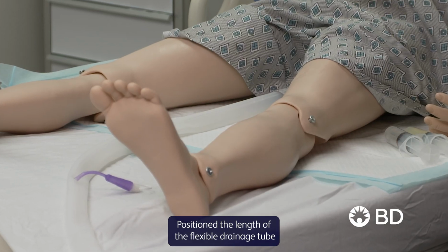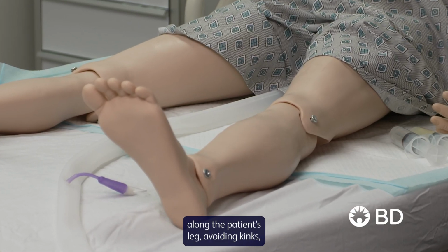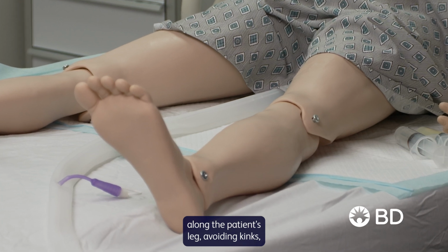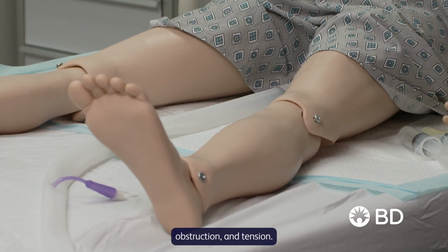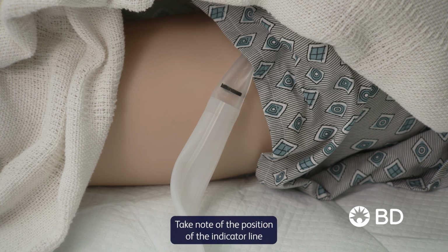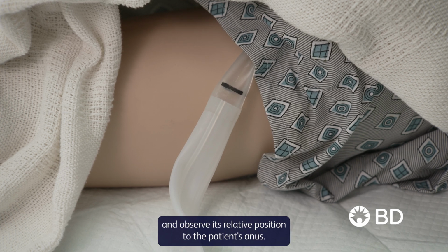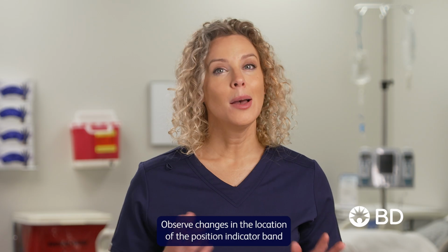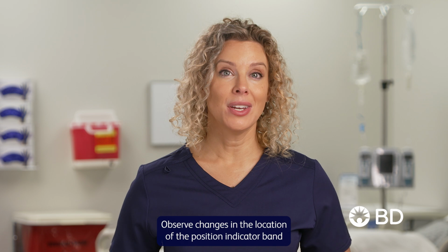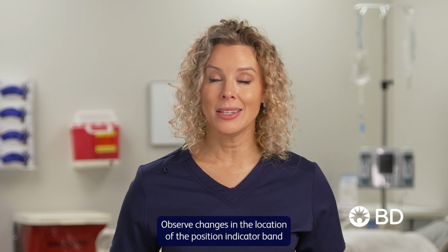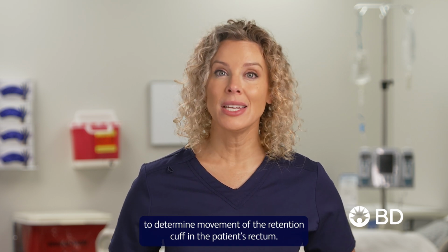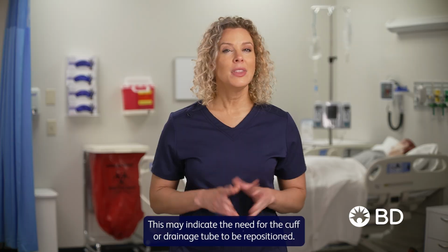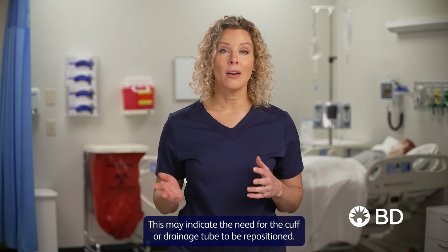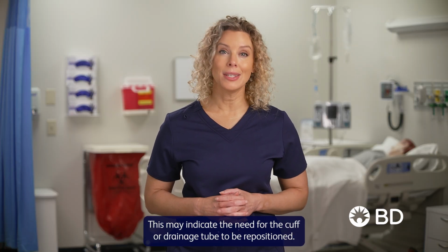Position the length of the flexible drainage tube along the patient's leg, avoiding kinks, obstruction, and tension. Take note of the position of the indicator line and observe its relative position to the patient's anus. Observe changes in the location of the position indicator band to determine movement of the retention cuff in the patient's rectum. This may indicate the need for the cuff or drainage tube to be repositioned.